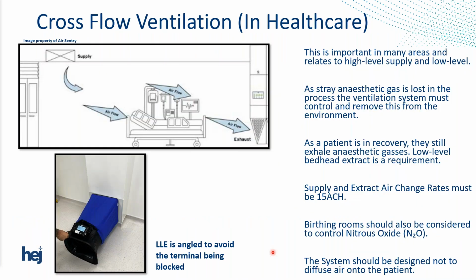Cross-flow ventilation in healthcare, here's an example. I've borrowed this image from Air Sentry, I'm sure he won't mind, but it gives a good example. Think of that as the mechanical vent, the supply air, with the patient sitting in this position. We bathe the patient in supply air and the mechanical system removes any contamination. If you imagine the patient exhaling anaesthetic gas in that position, the system should be able to take that away and discharge it into the atmosphere or wherever.